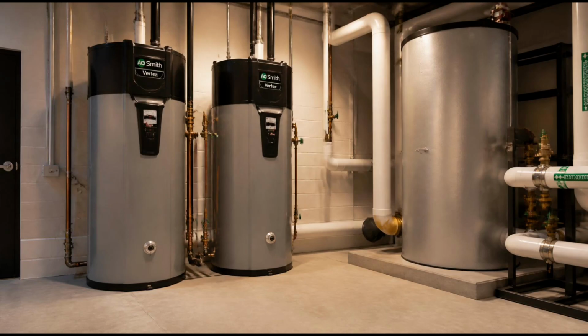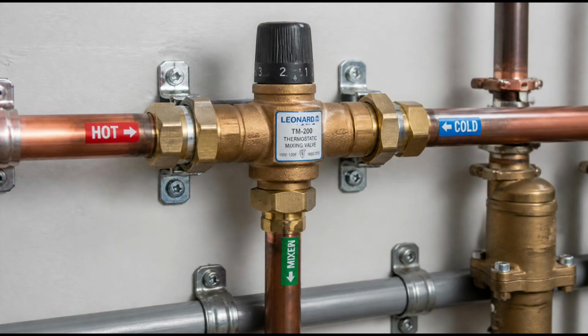Whatever the heat source, the temperature at which hot water is maintained is a matter of careful consideration. Too cool, and the water may not serve its purpose as well, and more critically, it can create conditions in which harmful bacteria, particularly Legionella, can survive and multiply within the system. Too hot, and there is a risk of scalding at fixtures, particularly in spaces where elderly people or young children may be present. The balance point for most commercial systems is around 120 degrees Fahrenheit at the water heater itself, hot enough to discourage bacterial growth, but not so hot as to be dangerous at the point of use.